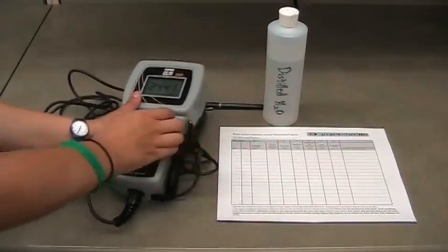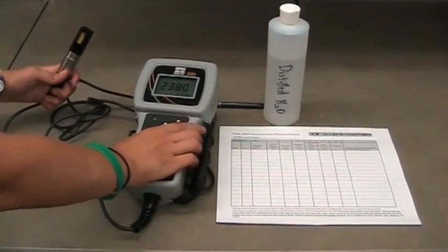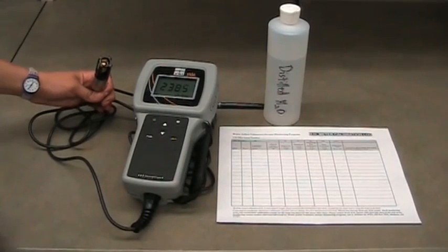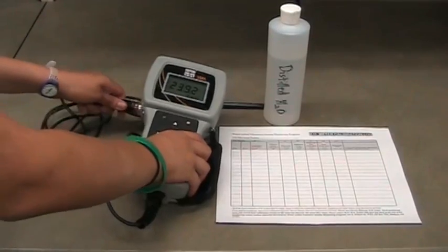Check the membrane, the gold part of the sensor, for tears, holes, or air bubbles. If damage exists, see the video on how to replace the membrane sensor tip. Shake excess water off the sensor and replace the probe in its chamber.